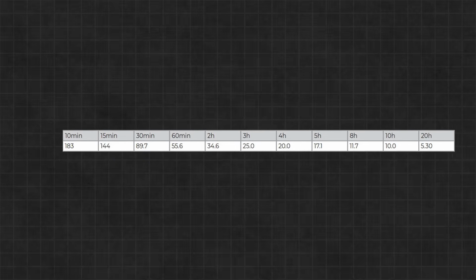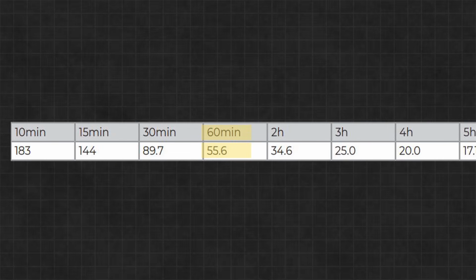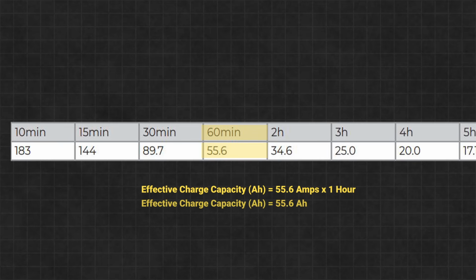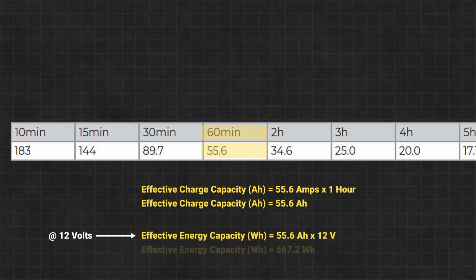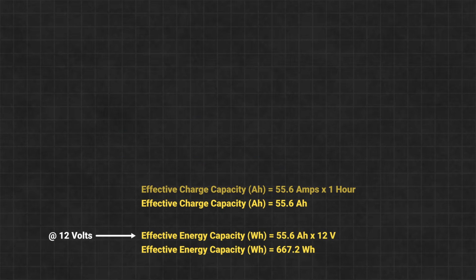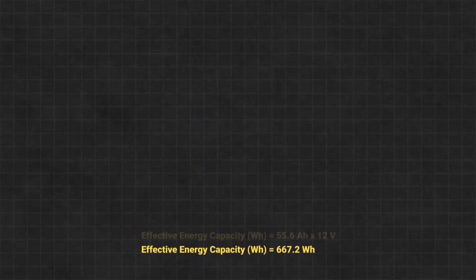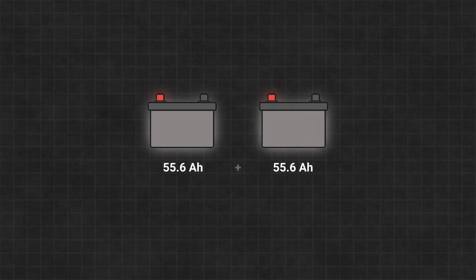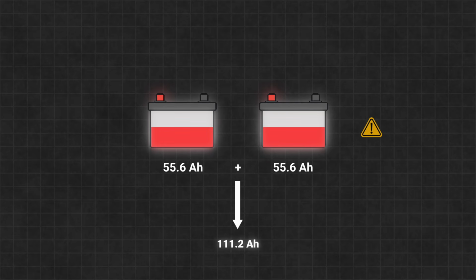For instance, if we refer back to the table from our earlier example, we can see that if the battery is discharged over 1 hour, it only provides 55.6 amp hours of usable capacity. But at 12 volts, we need the full 100 amp hours to reach 1200 watt hours. So one solution to this would be to add another battery, which would give us a little more than the 100 amp hours that we need. However, remember that lead-acid batteries shouldn't be discharged below 50% if you want to maximize cycle life. That means we would need at least 200 amp hours of effective charge capacity at 12 volts to meet our needs and to stay above 50% depth of discharge.